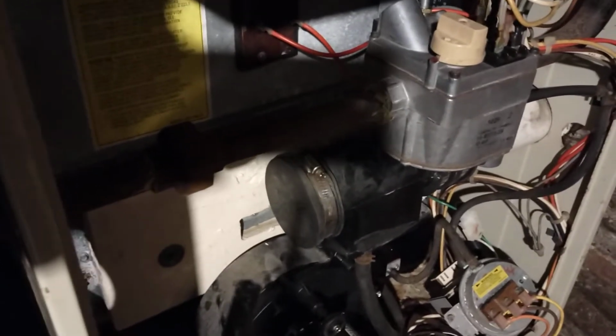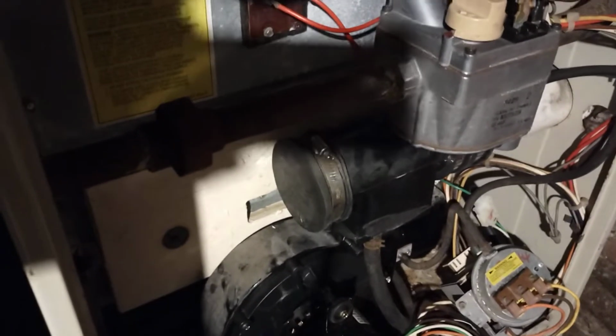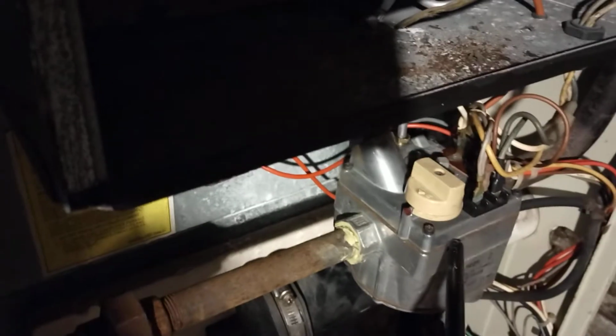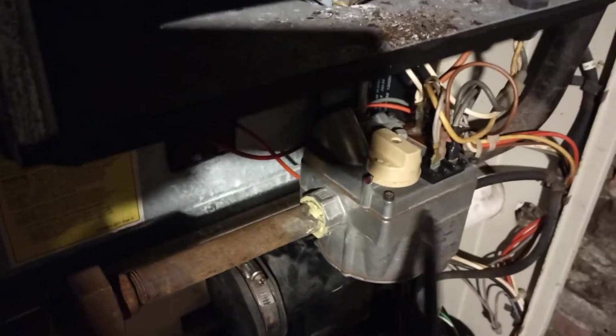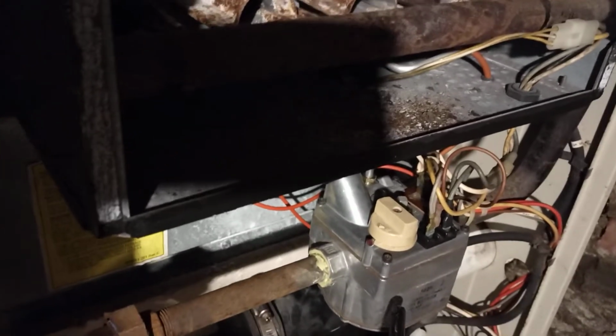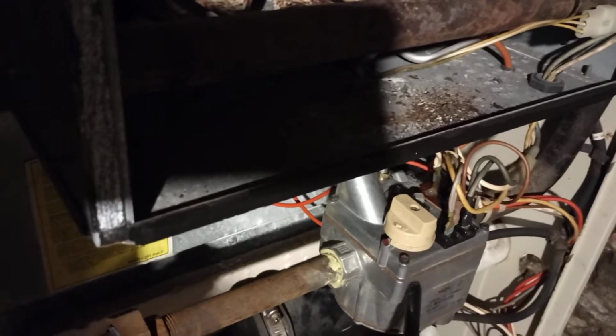So our first step was to replace the fan blower inducer motor. We've got another furnace just like this one on the other side of the building. We changed the gas valve from that one over there. When we took it out, we found that one was no good either. I was able to get a gas valve for this thing for $75 used on eBay.